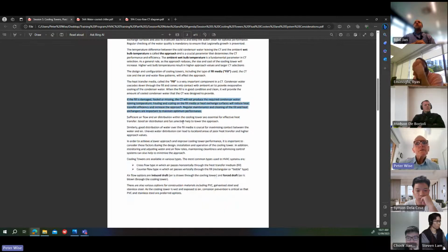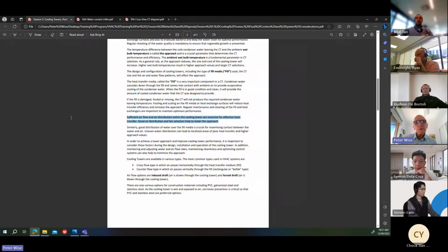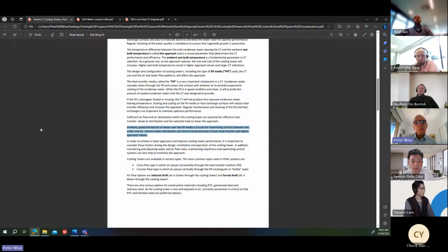Okay, as I've said, sufficient airflow and air distribution within the cooling tower are essential for effective heat transfer. Good air distribution and fan selection help to lower the approach. This normally is part of the job of the supplier: you tell them what you want, and they will select the cooling tower, the fan, and the fan performance required. And good distribution of water over the fill media is crucial for maximising contact between the water and the air. Uneven water distribution can lead to localised areas of poor heat transfer and higher approach values. And as I said, scaling. If you get scaling of the cooling tower, it's not going to work very well at all. So these are things that need to be considered when you're designing a system.